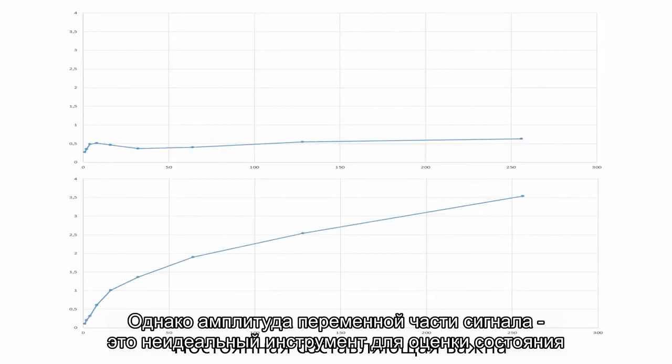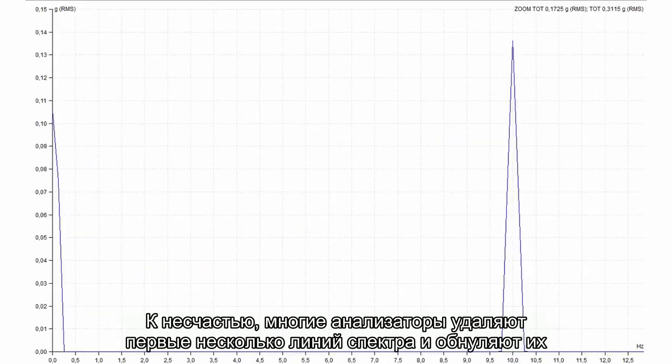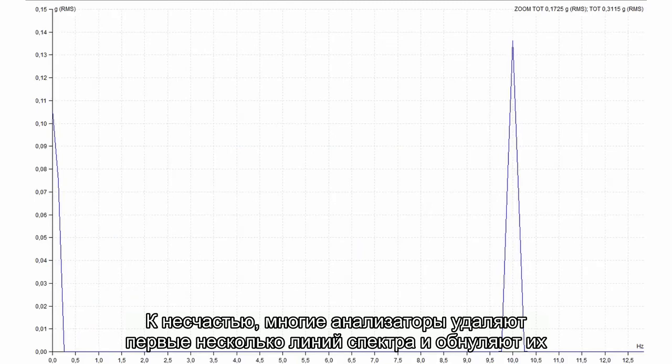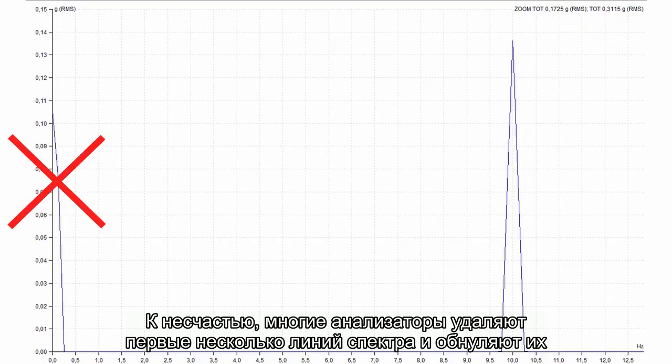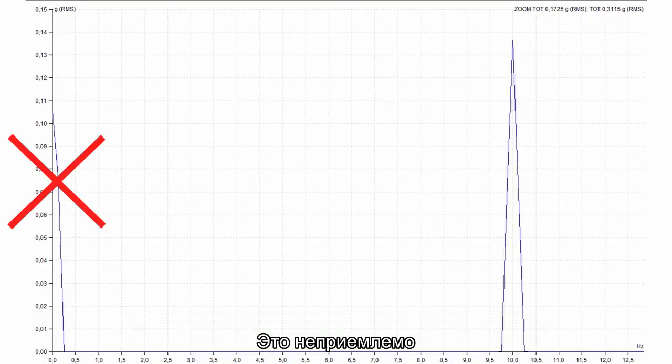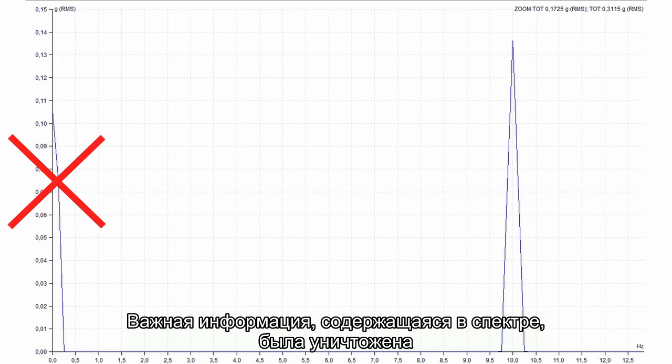But its AC amplitude is not a perfect tool for condition evaluation. Unfortunately, many analyzers remove several first spectrum lines and set them to 0. It is unacceptable. They destroy important information in spectrum.